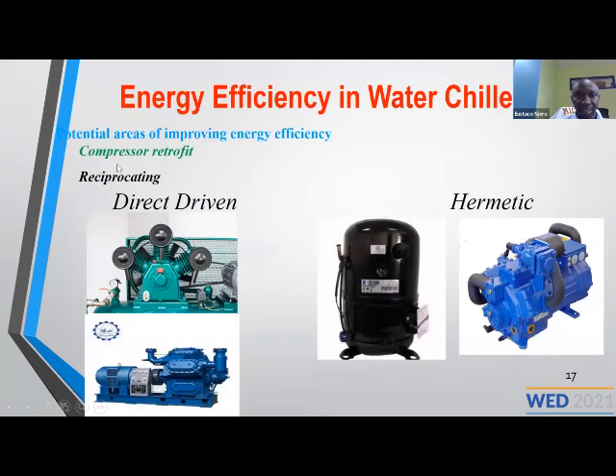So as we have seen, it is just a presentation to show you the types of reciprocating compressors we have. We have the direct driven ones, and we have the hermetic. The hermetic ones are where the compressor and the motor are all in an enclosed shell. These are used for small units, and you don't use them in very big units. The disadvantage is that once the compressor is faulty, you cannot easily service them. So they come in small sizes.